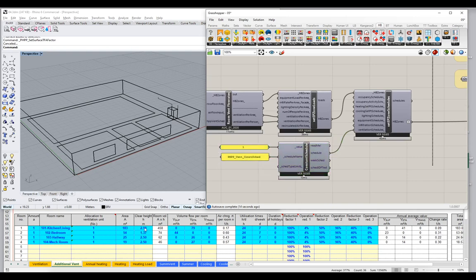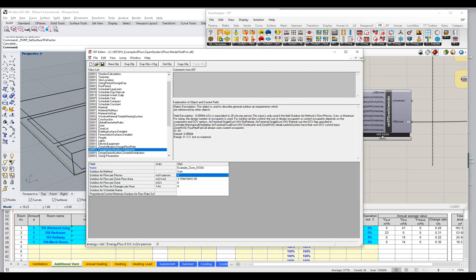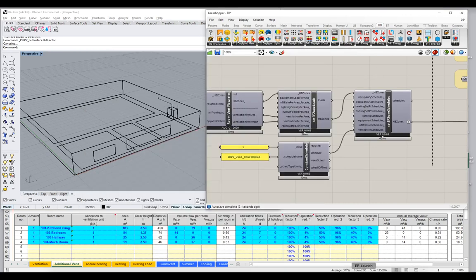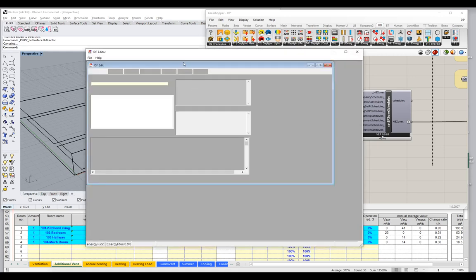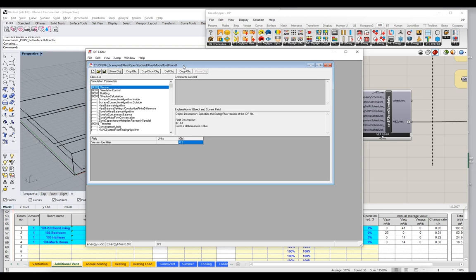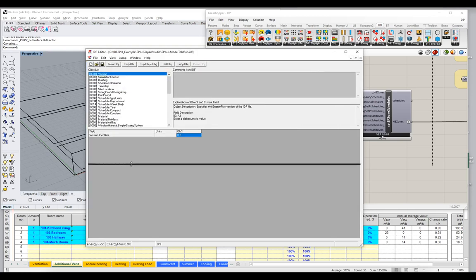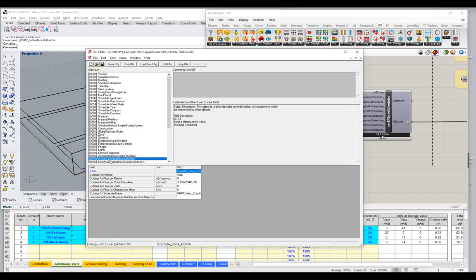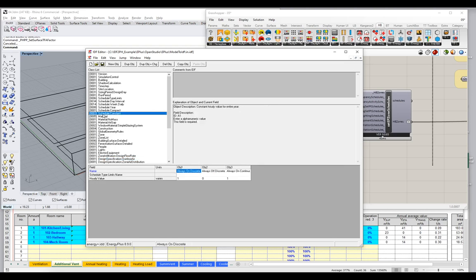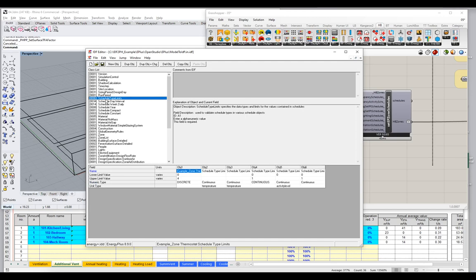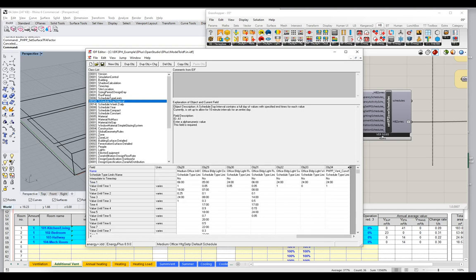So let me go back to our IDF and let's take a look. This has been updated, so I need to reopen it. I'll come down here to my design specification outdoor air. So these numbers are the same. But notice that my outdoor air schedule name has been set to PHPP ventilation constant schedule. So if I was to come up here to schedules, constant, I would find a couple different options here. There's our PHPP ventilation constant schedule, 24 hours a day, all day, every day.